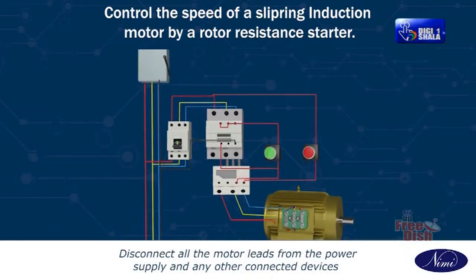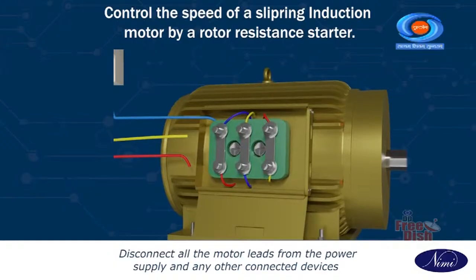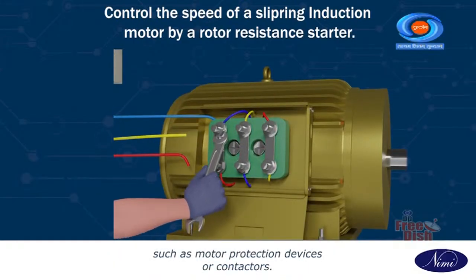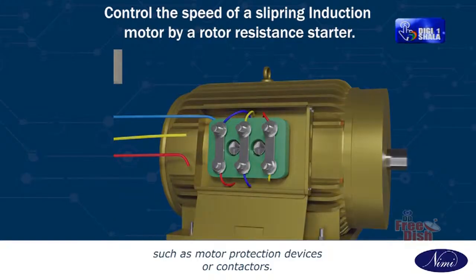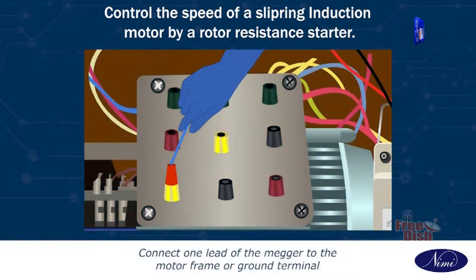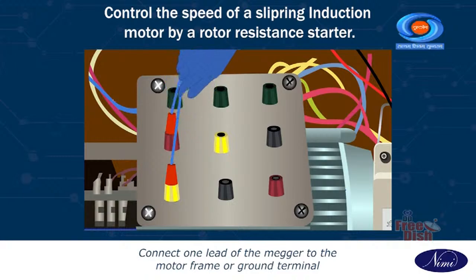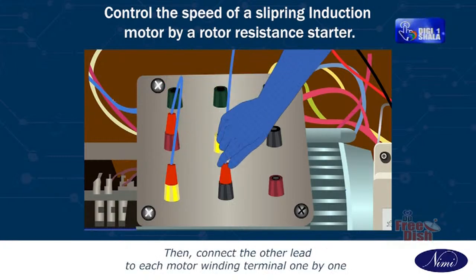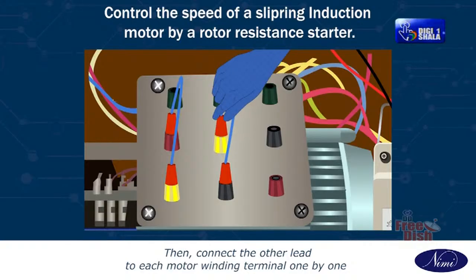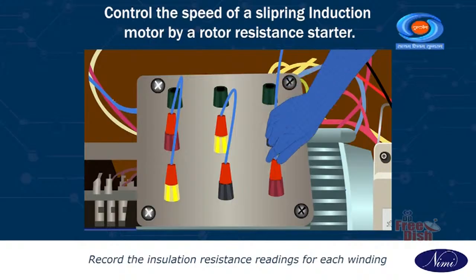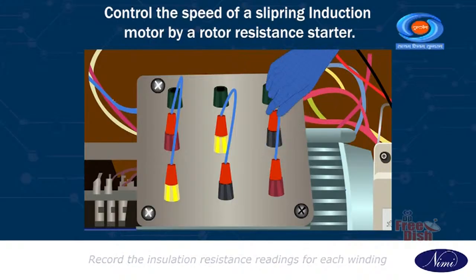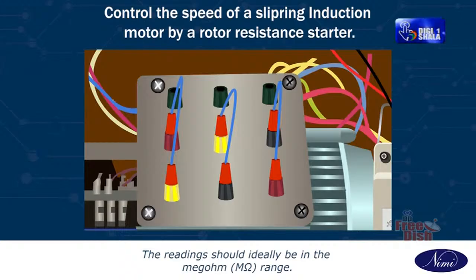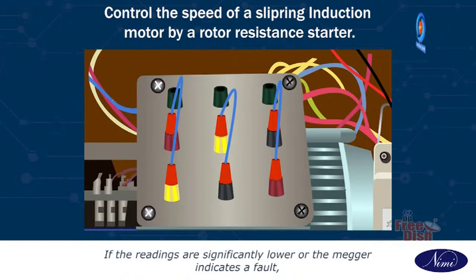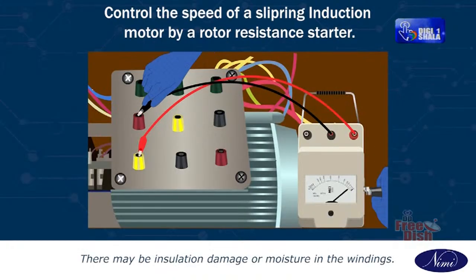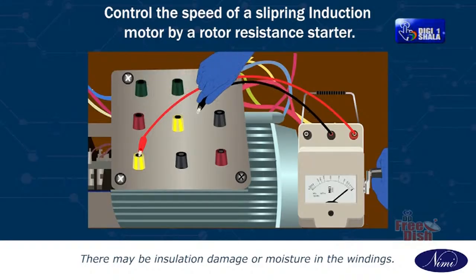Disconnect all the motor leads from the power supply and any other connected devices such as motor protection devices or contactors. Connect one lead of the megger to the motor frame or ground terminal. Then connect the other lead to each motor winding terminal one by one. Record the insulation resistance readings for each winding. The reading should ideally be in the mega ohm range. If the readings are significantly lower or the megger indicates a fault, there may be insulation damage or moisture in the windings.